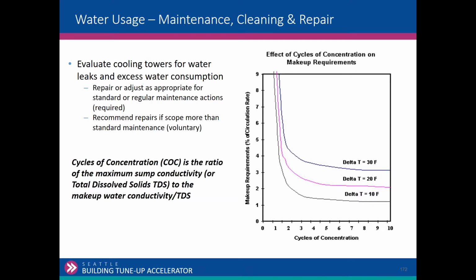And just the focus here to keep in mind is that we don't want to waste water. And so when we do the cooling tower workshop, you'll learn more about this, but it's all about cycles of concentration. What is the ratio of my sump water to potable water, my makeup water? And we want to run fairly high. We have soft water in Seattle, so the higher the concentration ratio, the less water we use. And so we just want to make sure that the concentration ratio is appropriate for the situation, that we're not wasting water. And so that's the point of looking at conductivity, looking at the controller, verifying that we're not wasting water through the system.